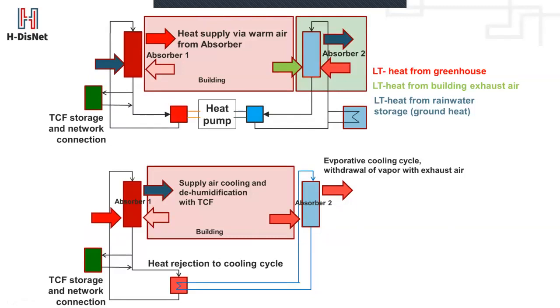In the cooling function during summer, it's a bit different. We use the second absorber as an evaporator, so we have normal water instead of the desiccant fluid. We use the exhaust air to be humidified and to cool the water, and the cool water cools the desiccant cycle, giving a kind of natural cooling process.